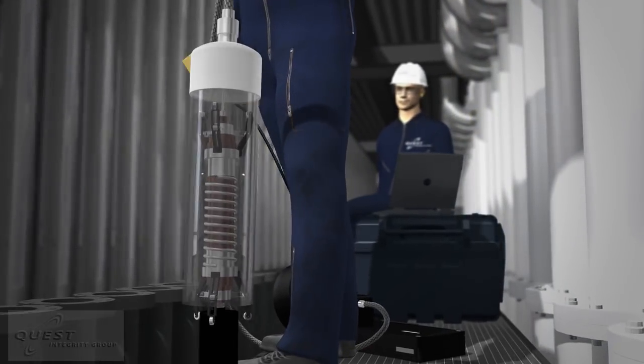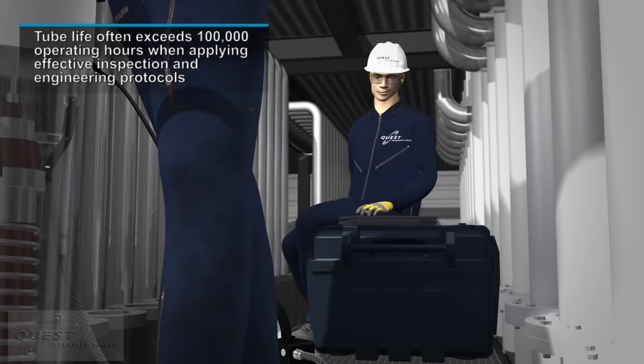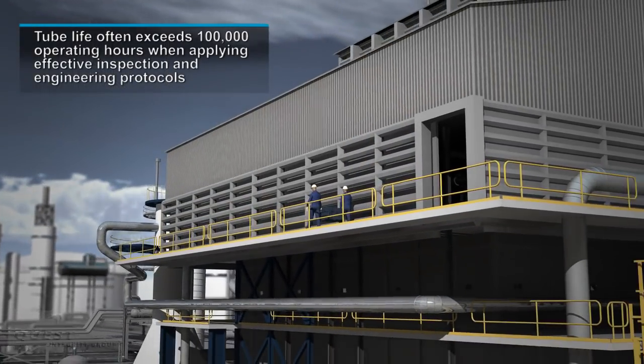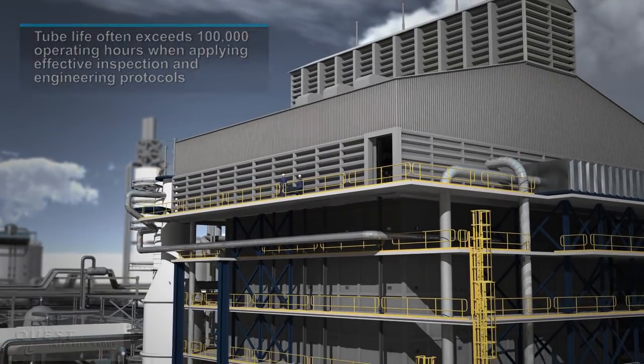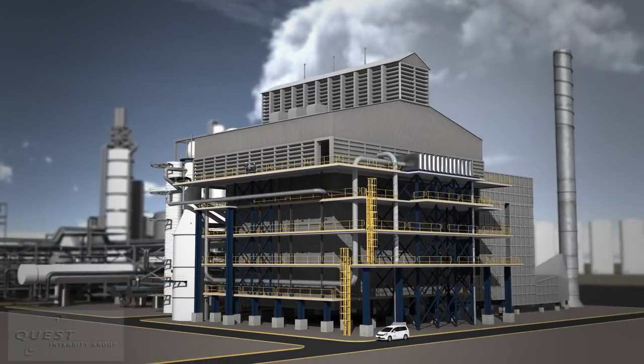The LOTIS test results provide a significant quantity of diagnostic information, allowing plant engineers to manage and often extend tube life beyond the typical prescribed normal 100,000 operating hours. This information also assists plant operators in improving reformer output while operating within the integrity window.